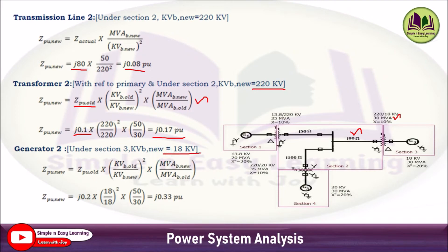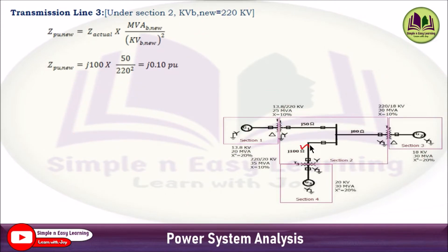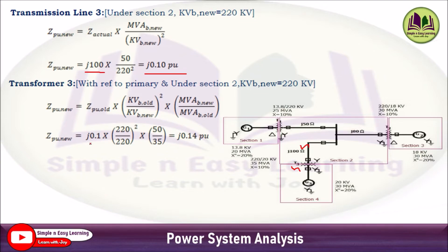For transmission line 3 (j100 ohm, section 2): Z_pu = j100 × 50/220² = j0.10 per unit. For transformer T3 (HT side in section 2, rated 35 MVA, 220/20 kV, x = 10%): Z_pu_new = j0.1 × (220/220)² × (50/35) = j0.14 per unit. You can refer to either the HT side with section 2 base kV or the LT side with section 4 base kV.